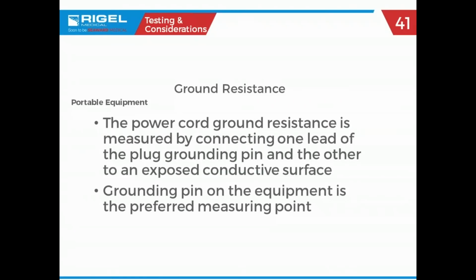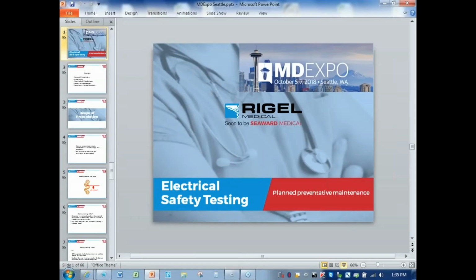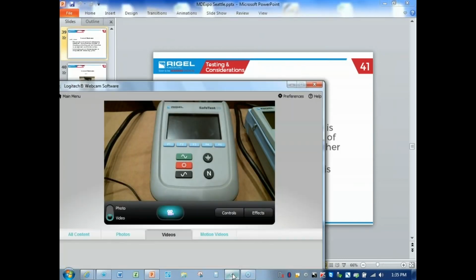So here we go, the good stuff. Ground resistance, ground continuity, earth bond, all the same thing. Power cord resistance is measured by connecting one lead of the plug, grounding pin, and the other to an exposed conductive surface. Grounding pin on equipment is the preferred measuring point. So what we're going to do is our first demonstration here. And I have enough cords up here where I can get seriously hurt. And what's the current level that I have to worry about before I go? So what we're going to do, we are going to do this. We're going to find my glasses. There we go. All right. Here we go.